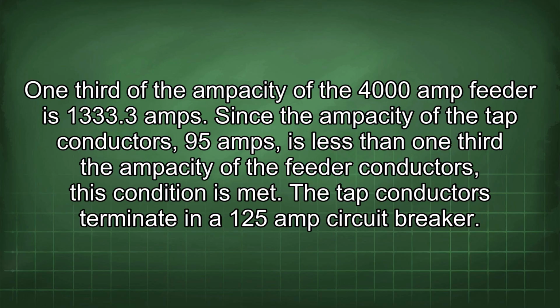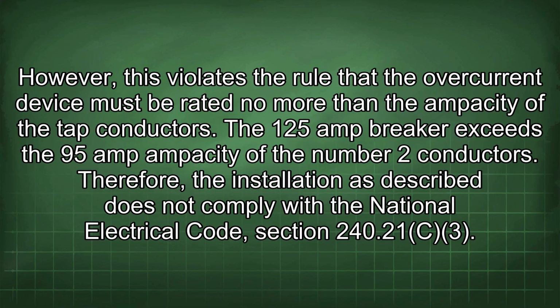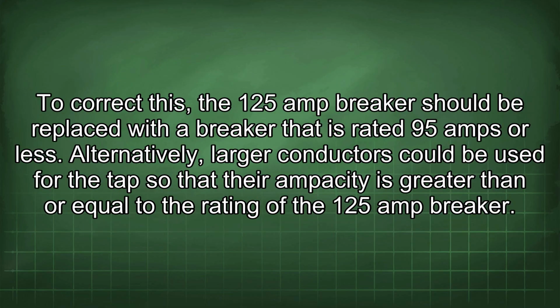The tap conductors terminate in a 125 amp circuit breaker. However, this violates the rule that the overcurrent device must be rated no more than the ampacity of the tap conductors. The 125 amp breaker exceeds the 95 amp ampacity of the number 2 conductors. Therefore, the installation as described does not comply with the National Electrical Code, Section 240.21(C)(3). To correct this, the 125 amp breaker should be replaced with a breaker that is rated 95 amps or less. Alternatively, larger conductors could be used for the taps so that their ampacity is greater than or equal to the rating of the 125 amp breaker.